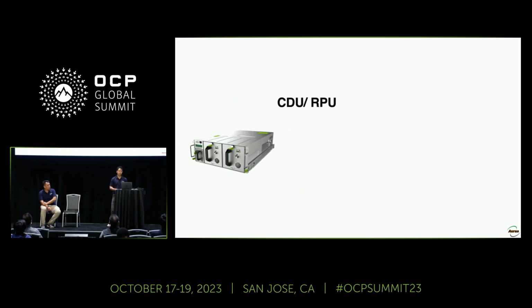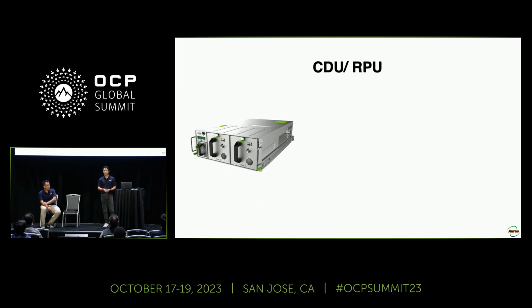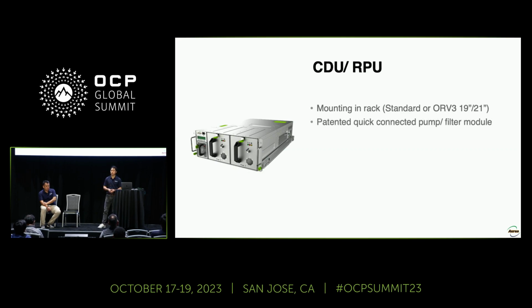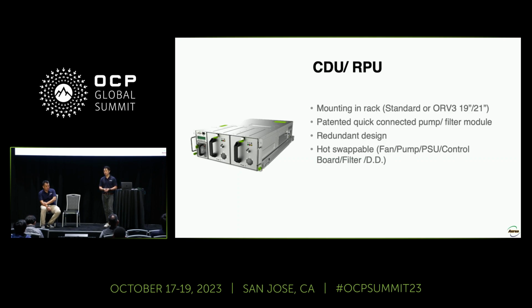And next will be our CDU. Our CDU has some of these features. It can mount in a rack, no matter if it's a standardized rack or ORV3 rack. We have the patented quick connect pump filter module. All of our design is redundant, just in case of failure. And they are all hot swappable, including the fan, the pump, PSU, control board, filter and DC to DC converter. And it can be remotely controlled, realized by the web or the Redfish API.